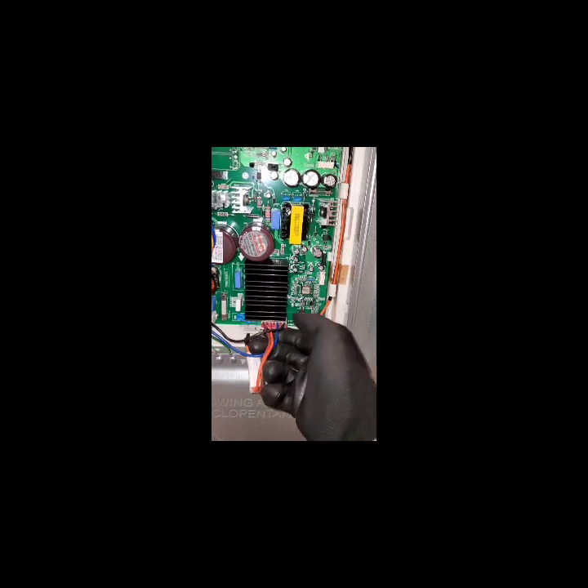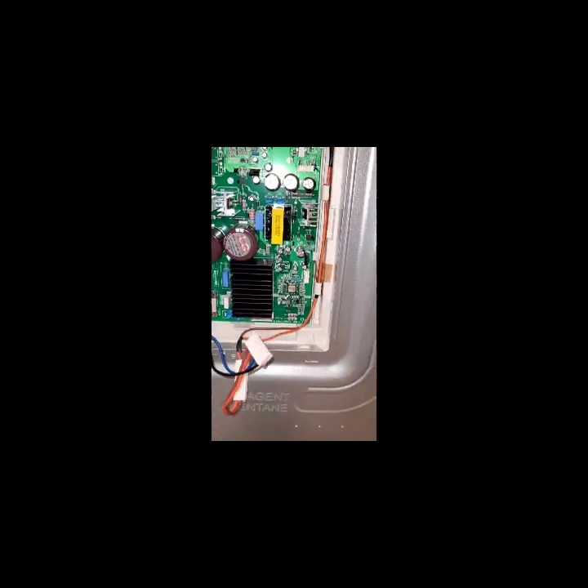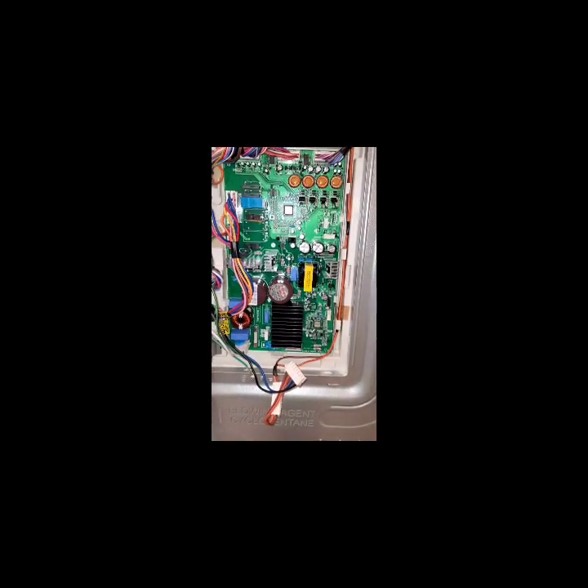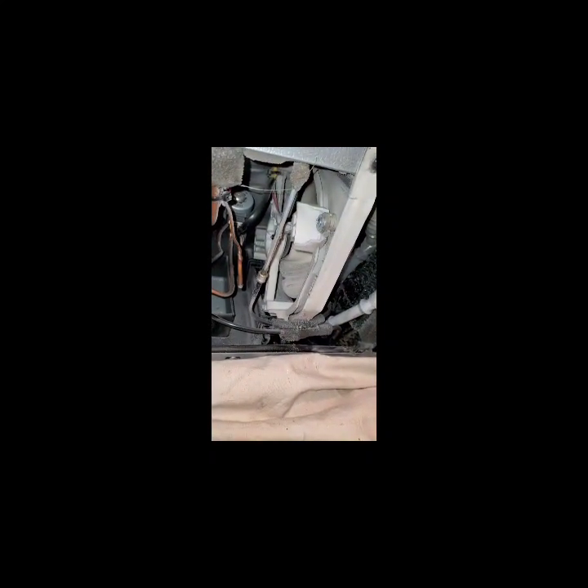Remember step one: we're going to disconnect the molex. Now while I'm disconnecting the molex I'm going to hook up my leads to the black and blue, common and power. Make sure that you got your volt meter set up on AC volts. The refrigerator right now is equalized, that's why my low side is about 60. Bear with me, this was shot in the customer's home. I'm doing a voiceover in my studio.